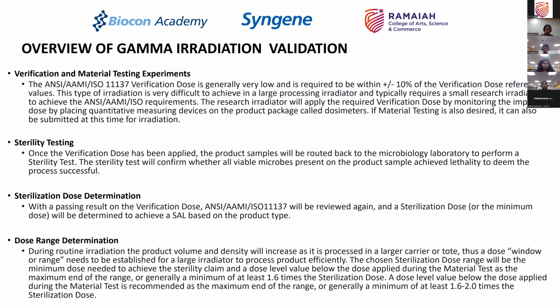How do you determine this? You determine this by fixing the range from a minimum dose at which you achieved lethality, and then taking an assumption saying that I cannot go below 15, I cannot go below, let's say, 20. Therefore I want to keep at least something higher than that, and that higher is at least 20% higher or something like that. Again, ISO 11137 gives some light onto how to determine this range also.